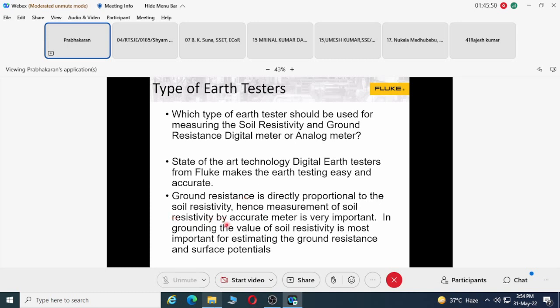That means you first have to find what is the soil resistivity, and then design it so that you can achieve the best resistance levels. Especially for critical applications and communication systems, people recommend very close to 2 ohms or less. For some applications it may be 5 ohms or less. In calibration laboratories, it may need to be 1 ohm or less in the electrical grounding systems.